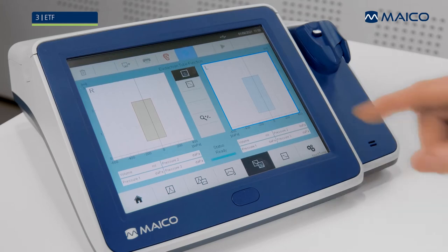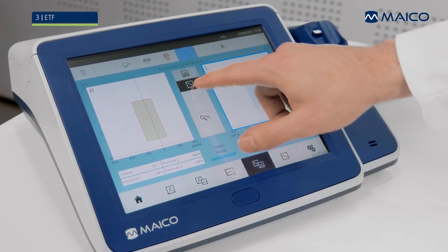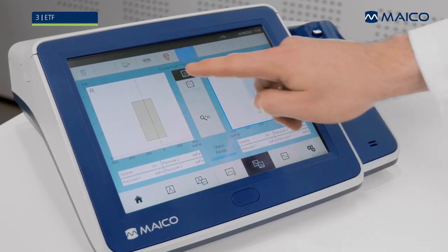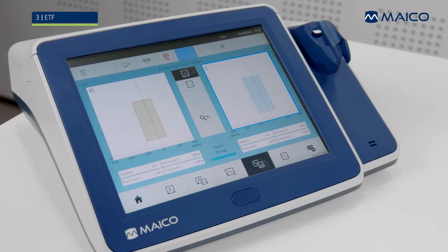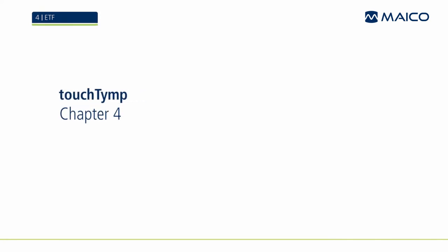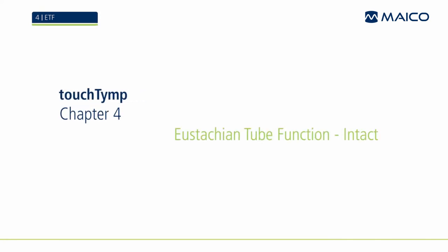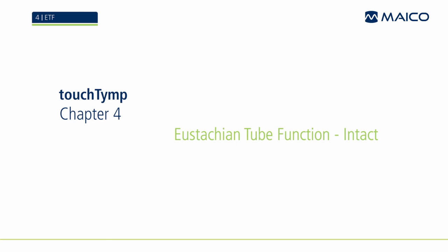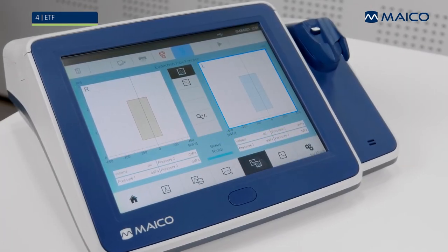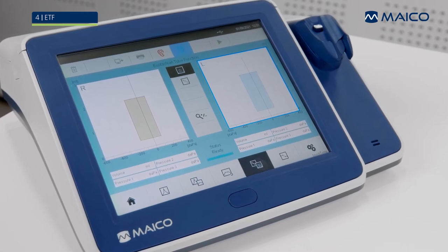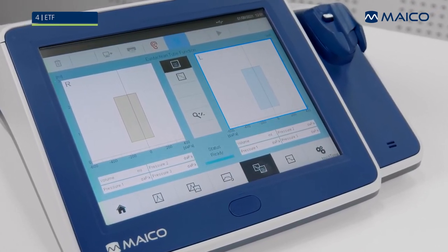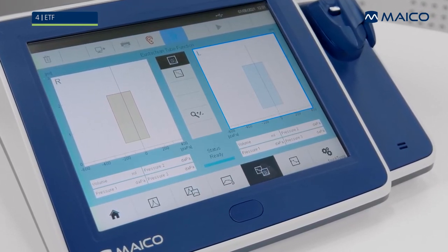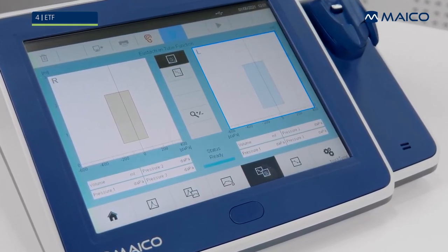Select the test type ETF Intact or ETF Perforated from the ETF module. ETF Intact is the default selection when the module is entered. ETF Intact is performed by measuring three tympanograms on a multi-layer display. The execution of the test is assisted by instructions displayed in message boxes. The order of instructions or maneuvers displayed can be configured in the settings.